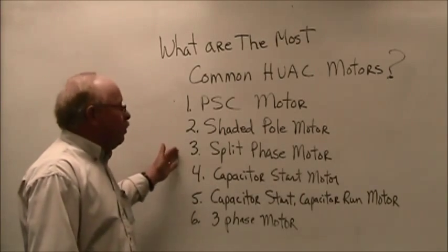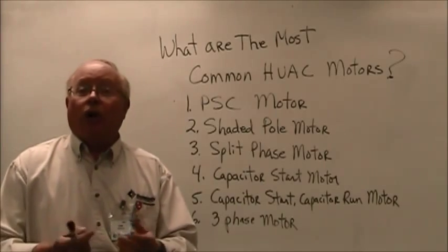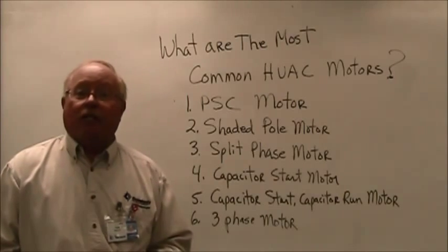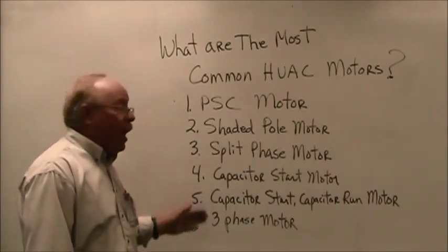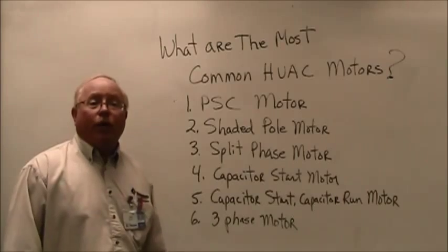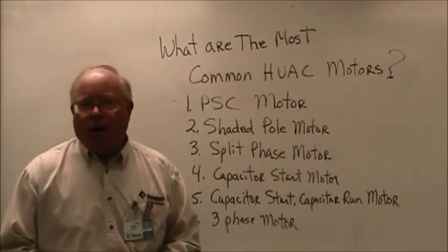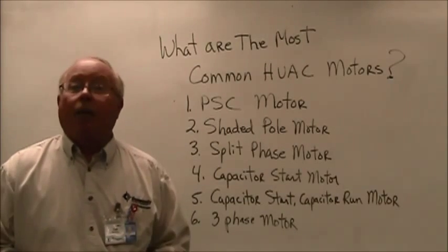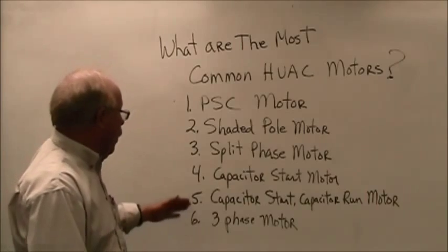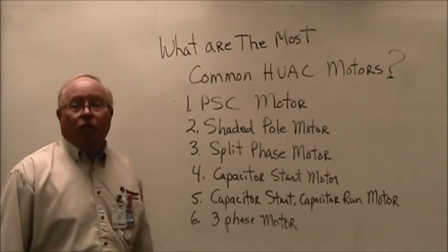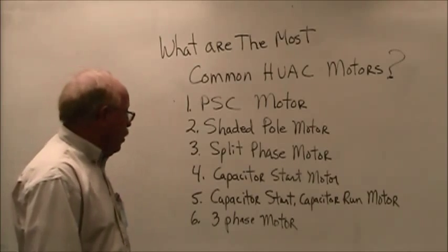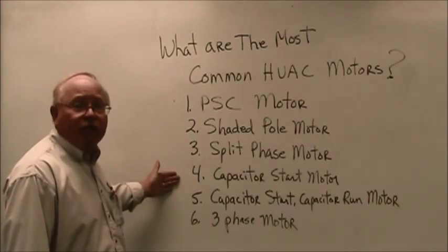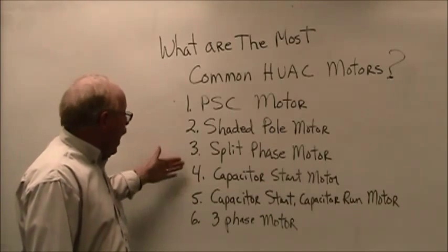When we look at the split phase motor, once again we're looking at a higher torque motor, and this motor is good for pumps and good for some of the air applications also. But when we need a real high torque motor because we have to overcome head pressure — such as in a compressor or head discharge pressure such as in a pump or when we're pumping water somewhere — then we have the capacitor start motor, a very high torque motor.